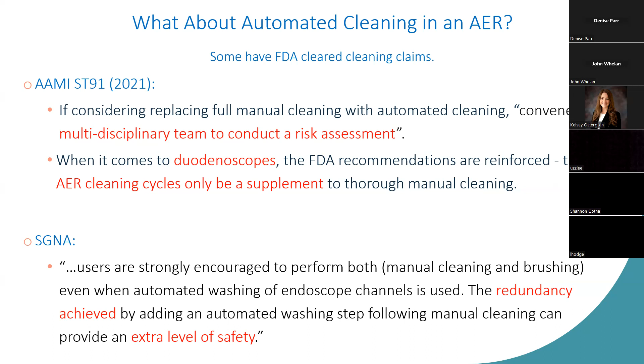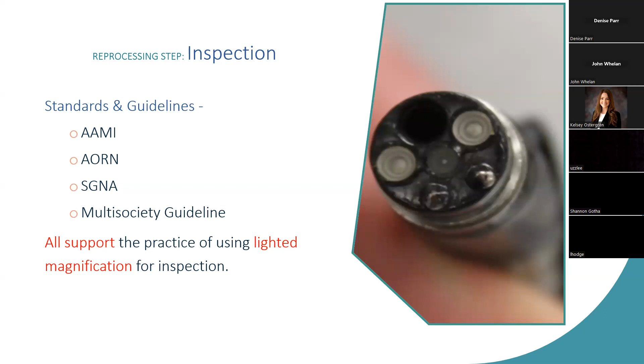We emphasize that manual cleaning is the most important step in removing the microbial burden. To better ensure that cleaning was as effective as possible, we need to inspect the scope. All the major professional societies and standards organizations support the practice of using lighted magnification for inspection to go beyond what we can just see with the naked eye. As part of my role as an educator, we provide consultative reviews at facilities. It's one of the services we provide. And unfortunately, even in 2024, it's not uncommon to see no inspection occurring after manual cleaning. They say they're looking at it as it goes through, but we need to purposely stop and make sure that it's clean enough to keep going and not damaged.